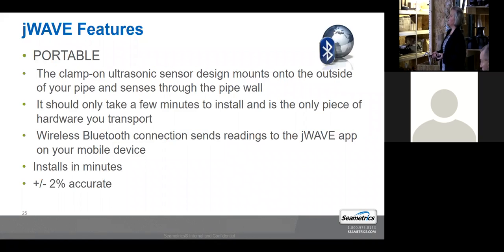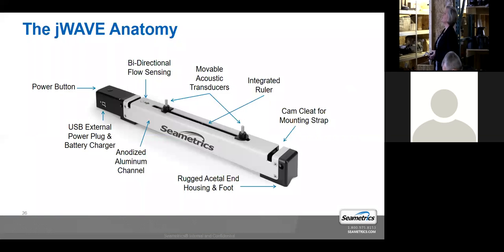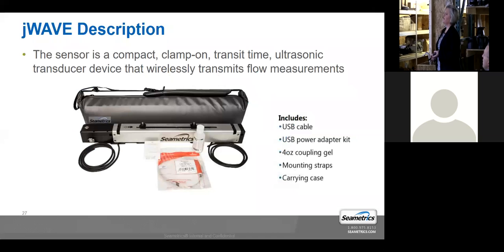Again, this one's portable. It's plus or minus 2% accurate. So if you have any of those propeller meters or mechanical meters out there, those are plus or minus 2% accurate. It's typically the manufacturer spec on them. This would be a great tool to stick in line and compare the accuracies. If you guys are interested or you want any more info on it, you can come talk to Paul or I, or you could check our website. This just explains what the different components are. Very easy to use. That's what I like about it.